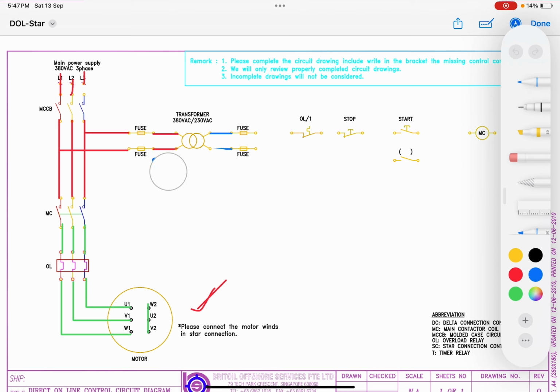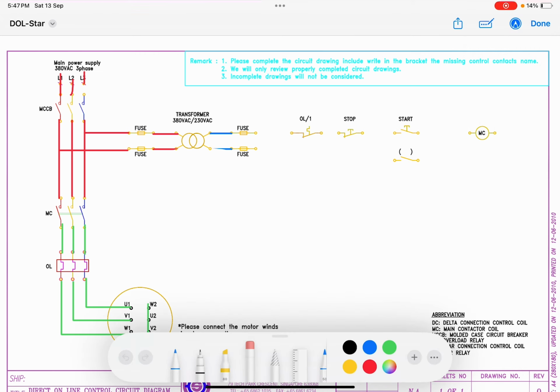Now in the control side, we have 230 volt AC. So how do we connect this circuit, and how is our motor going to work? All electrical circuits have 2 lines: one is your power line, the other is your neutral line. So the neutral line that is given here, we can connect like this. From here we can directly take this wire and connect it to the magnetic contactor. I will tell you why I am connecting it like this.